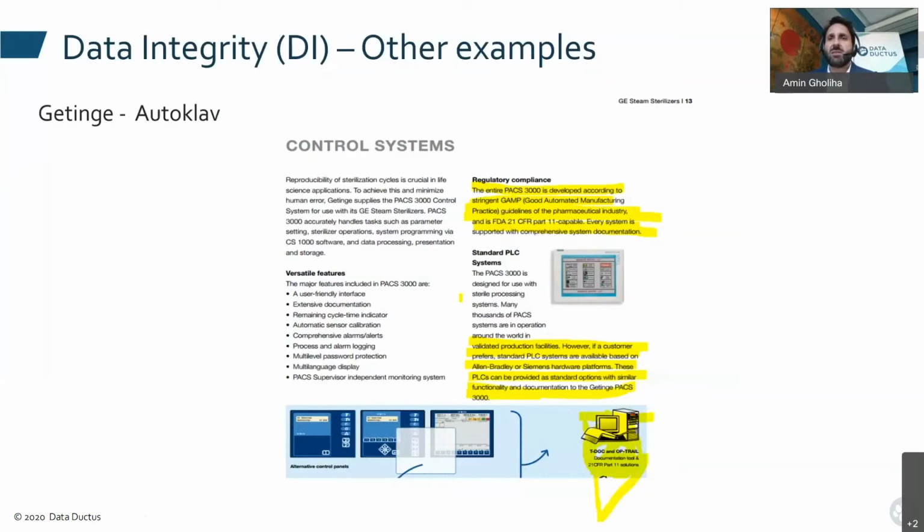But many vendors don't buy such software because they don't have good validation routines to validate everything. Therefore they have sterilization machines that don't have all the technical aspects needed for full data integrity, basically. This is a mistake that I know many companies make. So when you put the requirements in for purchasing your machines, you need to have proper routines for how to do that, basically.